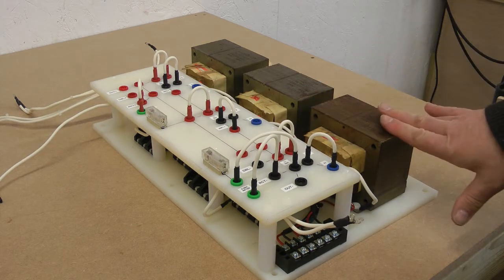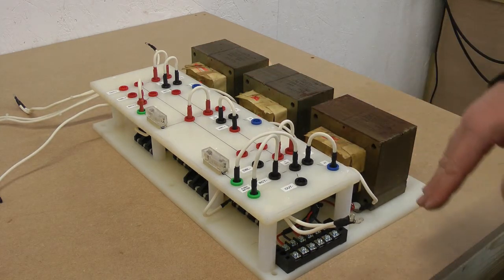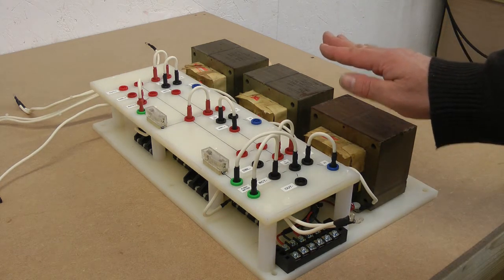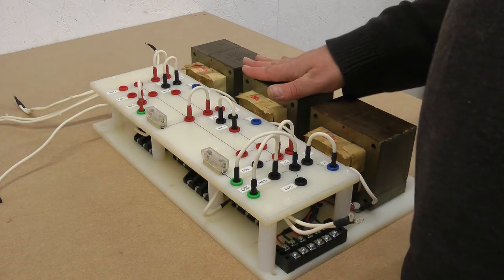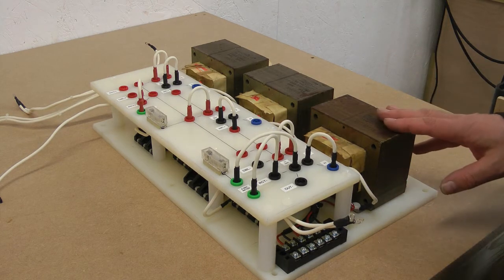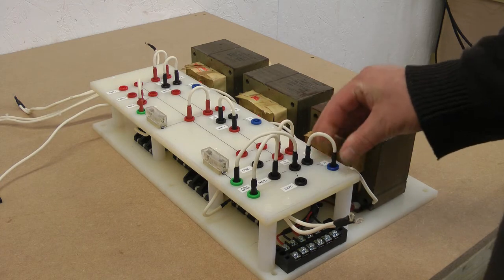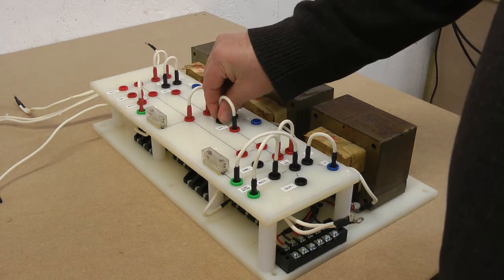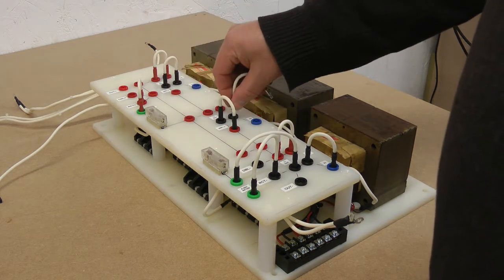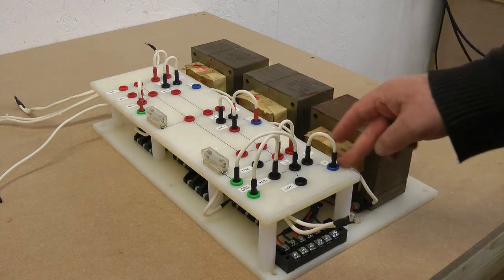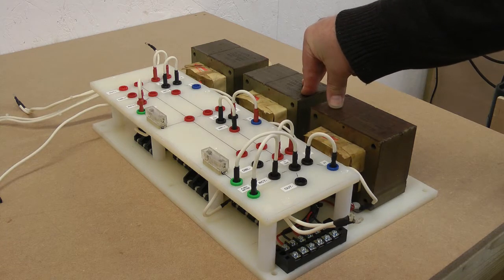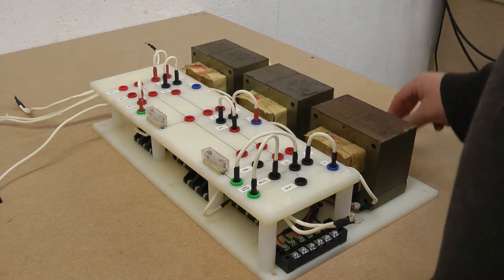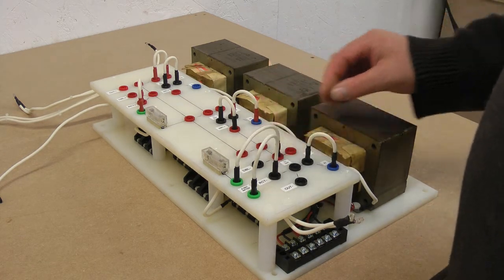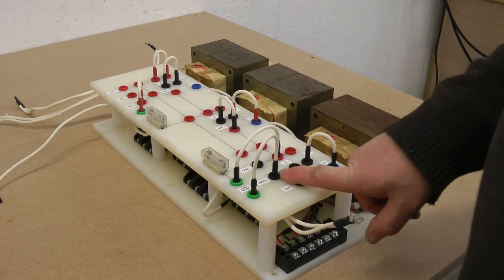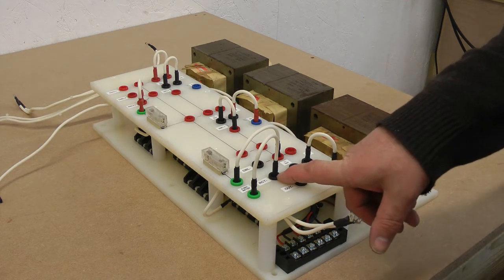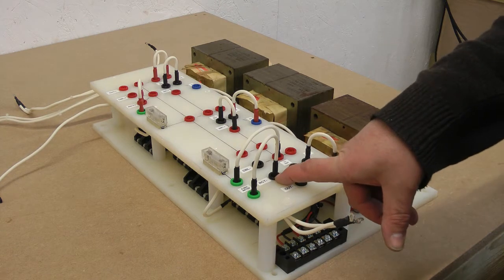Now, if I wanted to do a 3 series, then I've got to rearrange this quite considerably, because like I said, this would be a negative end, so minus 3 kilovolts. This will be plus 3 kilovolts. This will take it up to plus 6 kilovolts. So in a 3 series situation, I'm going to first of all connect the two cores down here. Let me borrow one of the other jumpers here. For example, that's going to go down to there. So the two cores are now connected together. Let's take that one away. I'm going to be using the positive output from this one through the fuse back out into the rectifier. Okay, so that's now going to produce minus 3 kilovolts.